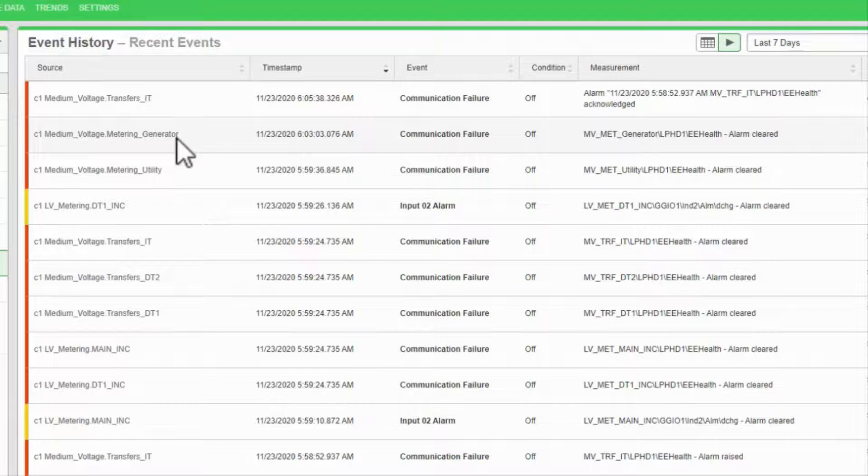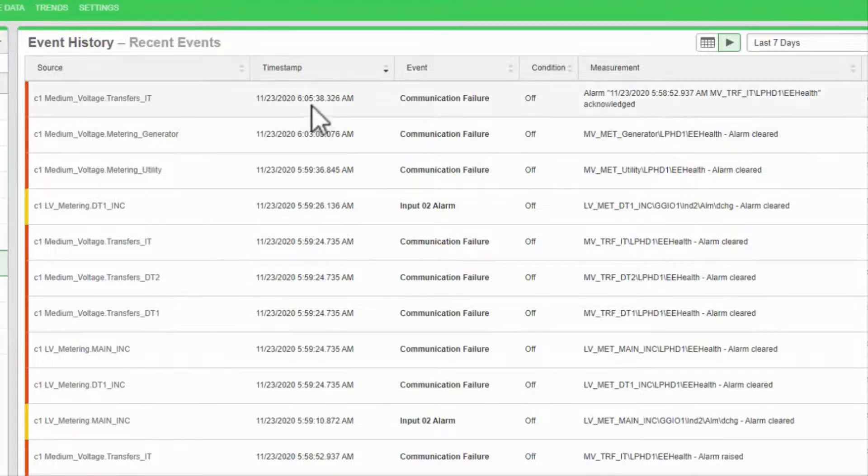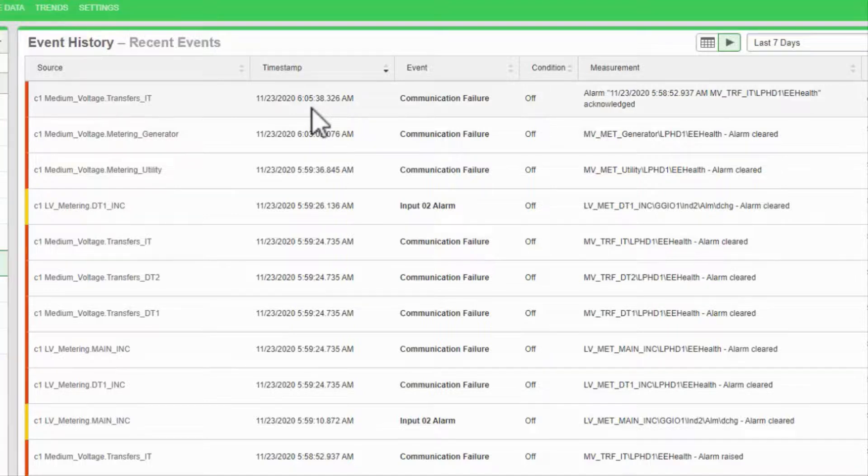For example, if a fault occurs in your network, this view will give you an exact timestamp of when each breaker trips and in what order, down to the millisecond if the hardware supports it. This is an excellent source of post-event analysis.